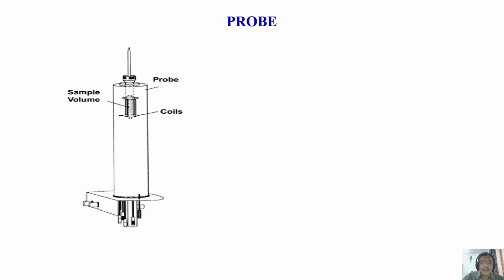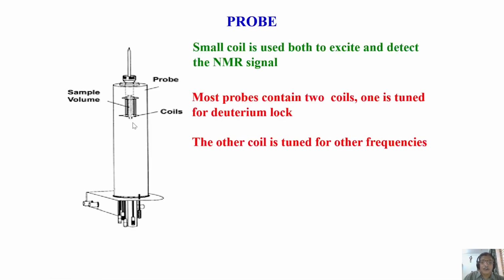Afterwards, the free induction decay which is induced is induced in this coil only. This acts as a receiver coil, both as a transmitter and as a receiver coil. And then the signal is collected and fed to the spectrometer, of course amplified, pre-amplified, fed to the spectrometer for processing, like Fourier transformation, etc. But basically, the probe is the one which has the RF coil, which does the job of transmitting and receiving the signal. And a small coil, okay.